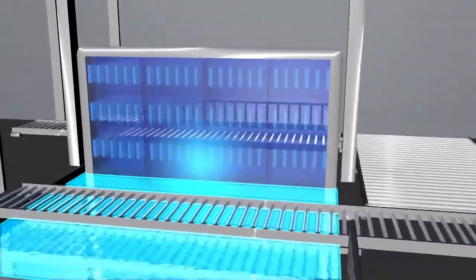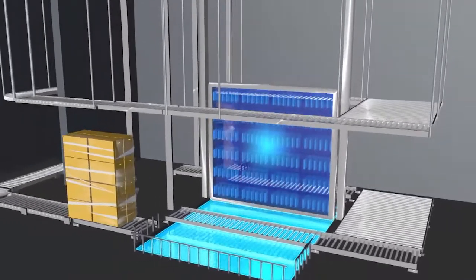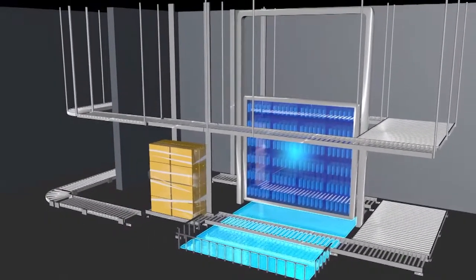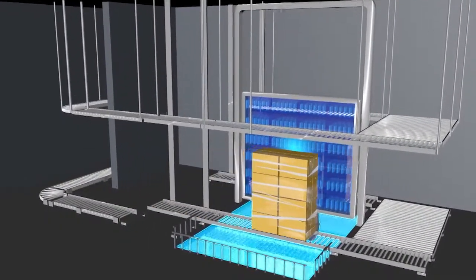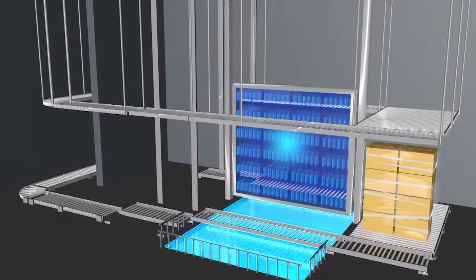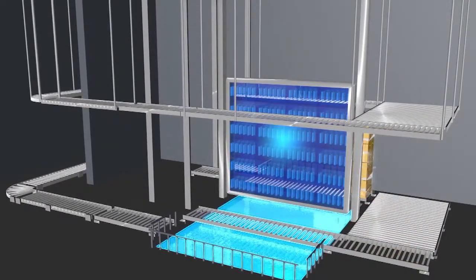In the core of a concrete labyrinth, the pallets pass a homogeneous field of gamma rays. The radiation source is cobalt-60, encapsulated in high-grade steel cylinders, which are lowered during unit standstill into an 8-meter deep water basin, the water column shielding off the radiation completely.